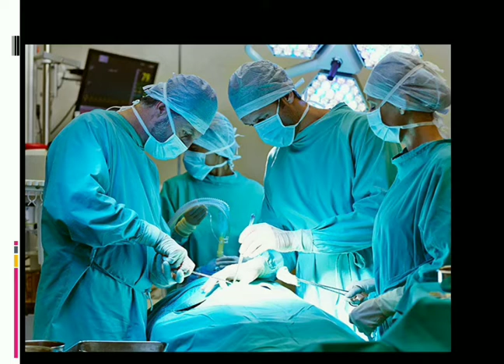And also in some surgeries where we have to put the patient under general anesthesia, we can use the ventilator. Okay, so how does a ventilator work? Basically, the ventilator is a power machine. It has an inlet through which the oxygen comes into the ventilator, and as we all know, oxygen comes into the ventilator in a dry state. So in order to humidify or add moisture to the dry oxygen, we use a humidifier in the ventilator.